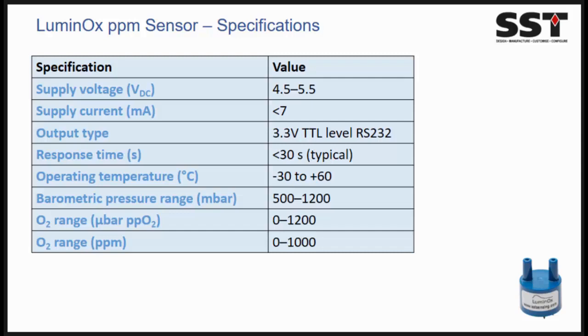We have the pressure sensor in there, so what we can do is actually monitor the partial pressure of oxygen. And again, this takes any pressure variations out of the equation. And this gives us a more accurate representation of the reading in ppm. So for example, if the pressure today was 1200 millibar and the PPO2 was 1200 microbar, then the ppm is 1000.